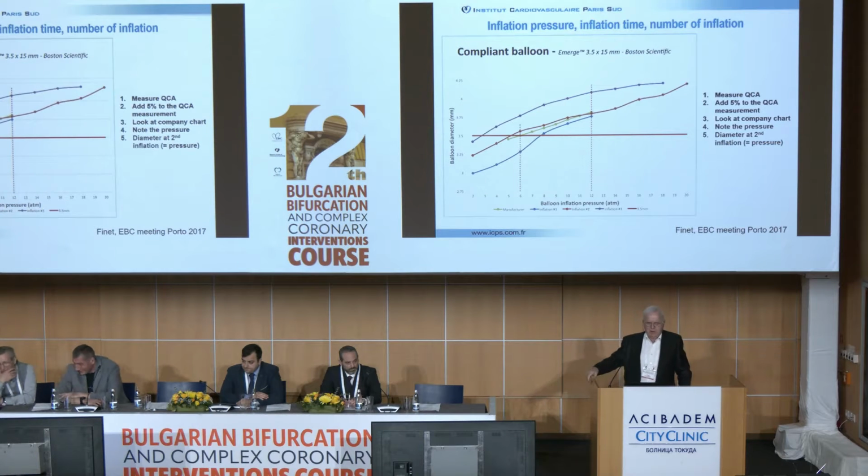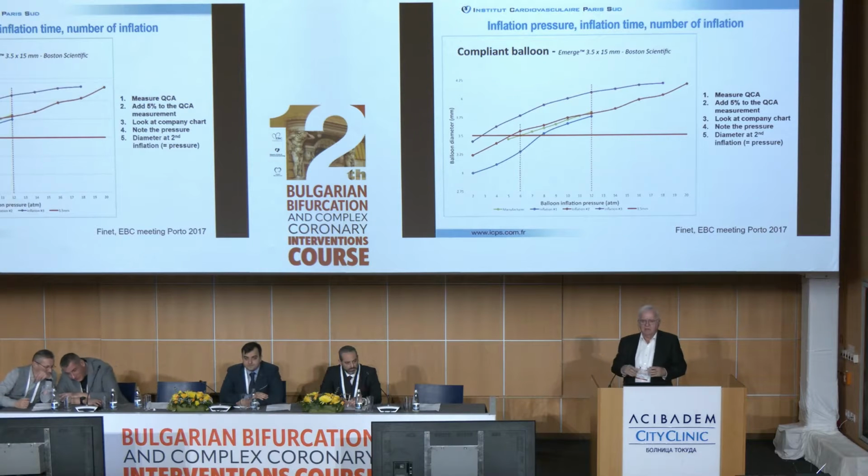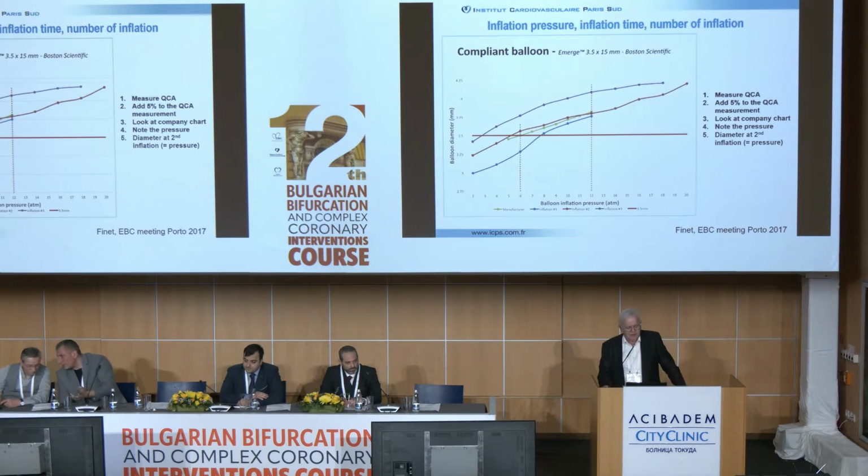After that, you have to know that balloons are not only elastic. Of course, the function of a semi-compliant balloon is to be elastic. You increase the pressure, you increase the diameter. But unfortunately, when you inflate a second time, there is the same phenomenon. Increase the pressure, increase the diameter, but not the same diameter, a bigger diameter. And if you do a third one, you get an even bigger diameter.